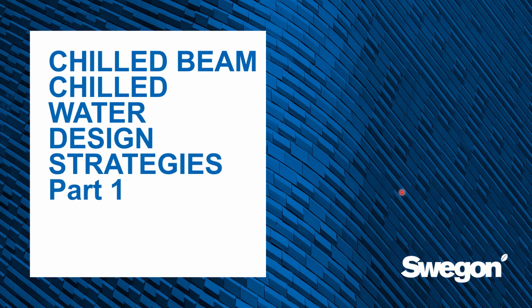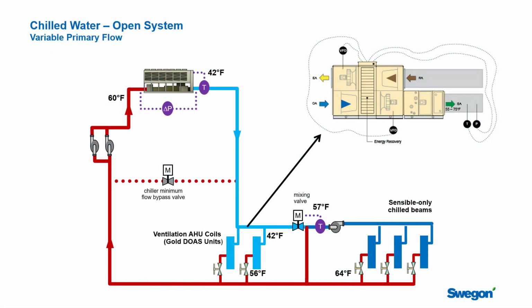In this video, we're going to consider chilled water design strategies for chilled beam projects. So here's the main layout. We're going to have a chiller plant, pumping system. Notice that for this slide and all the other slides, we're going to show you a variable primary flow chilled water plant. You could do this with primary, secondary as well. It won't matter to the overall discussion, but because it's variable primary flow, you can see we have a bypass that's controlled to maintain the minimum flow rate through the evaporators of the chillers.